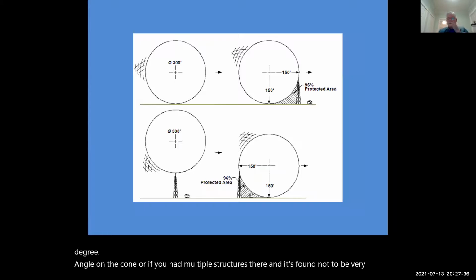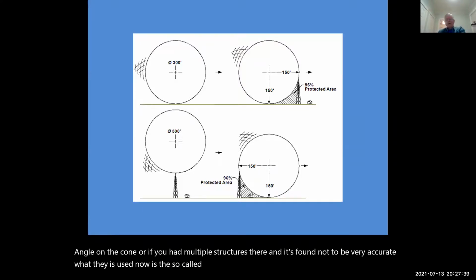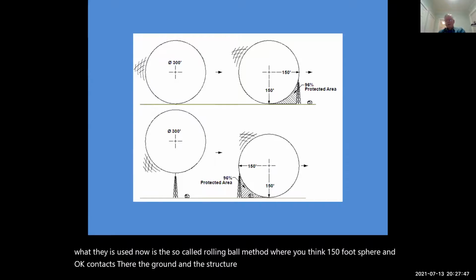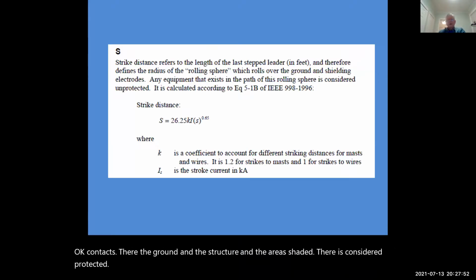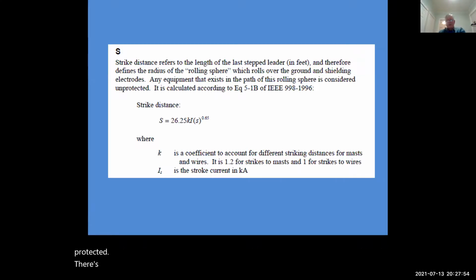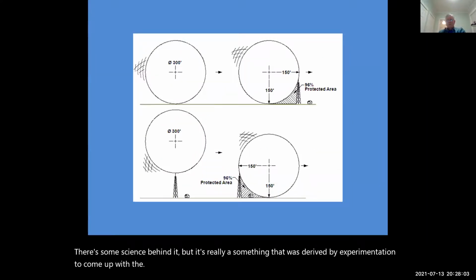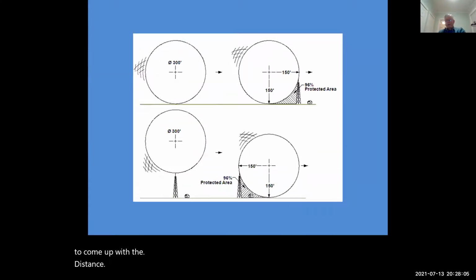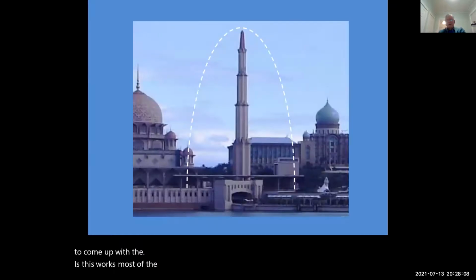What is used now is the so-called rolling ball method. You take a 150-foot sphere, it contacts the ground and the structure, and the area that's shaded there is considered protected. There's some science behind it, but it's really something that was derived by experimentation to come up with the strike distance. This works most of the time.